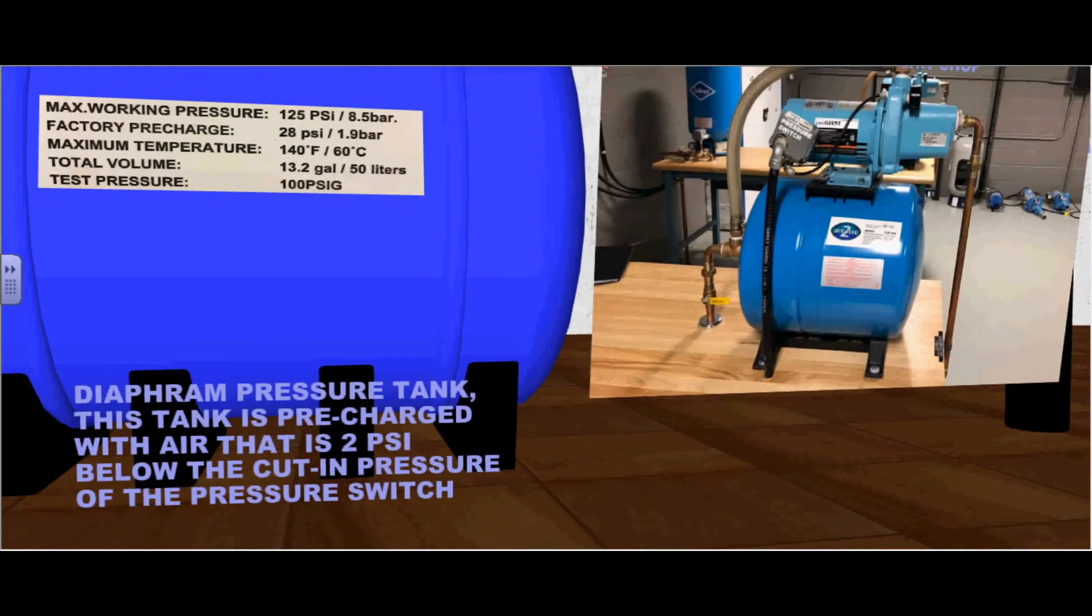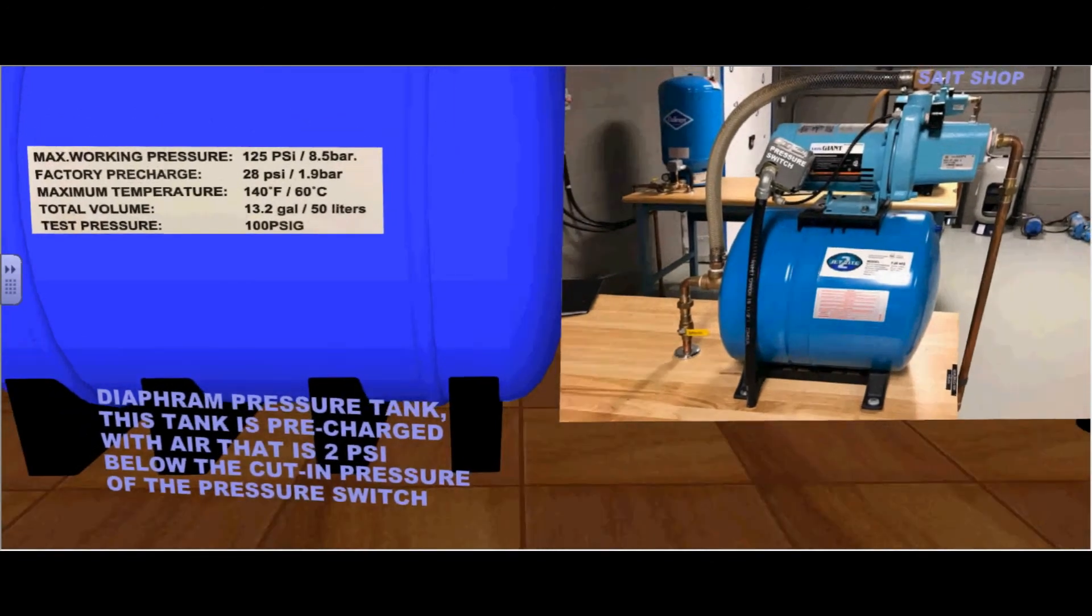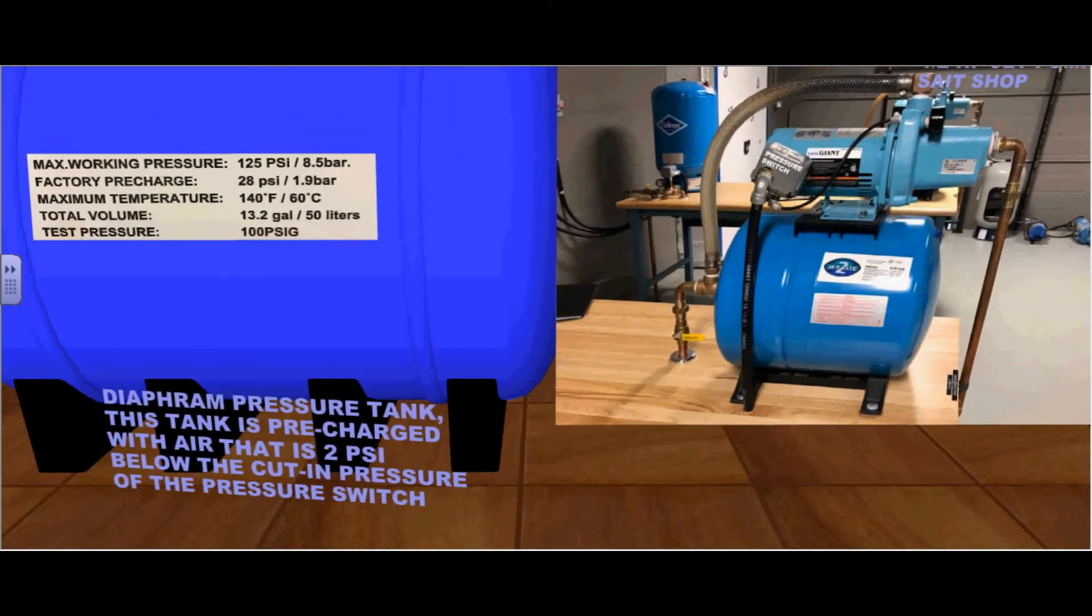This diaphragm pressure tank is pre-charged with air that is 2 psi below the cut-in pressure of the pressure switch. As you can see, it is factory pre-charged at 28 psi, 2 psi below the 30 psi cut-in switch.